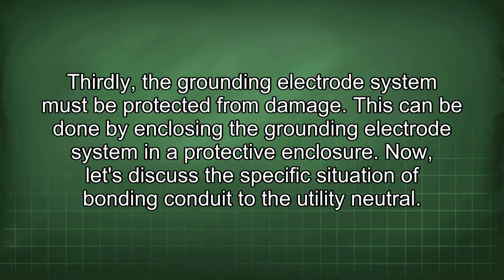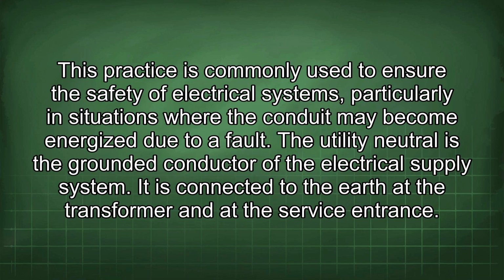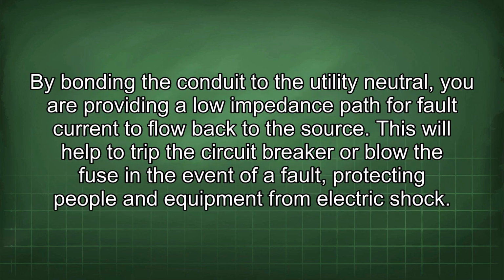Now let's discuss the specific situation of bonding conduit to the utility neutral. This practice is commonly used to ensure the safety of electrical systems, particularly in situations where the conduit may become energized due to a fault. The utility neutral is the grounded conductor of the electrical supply system. It is connected to the earth at the transformer and at the service entrance. By bonding the conduit to the utility neutral, you are providing a lower impedance path for fault current to flow back to the source. This will help to trip the circuit breaker or blow the fuse in the event of a fault, protecting people and equipment from electric shock.